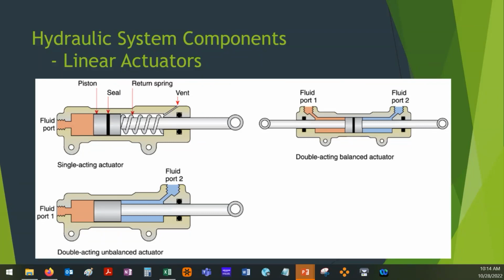And what's the difference between those? What is it referring to when we say balanced versus unbalanced? So the area that the pressure acts on, which is ultimately going to result in a force difference, right? So in this unbalanced actuator, bottom left, you can see the red on the left there, red-orange, I guess, is going to act on a lot bigger area than the fluid on the right, because on the right, there's no force on the area where the shaft is coming out. Now, I guess I should say there is force on the shaft, but it's not pushing it in a direction that's going to move it. Okay.